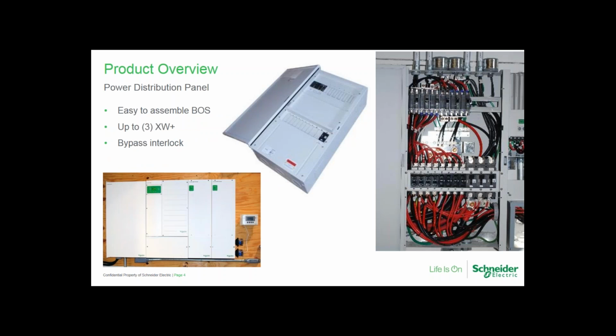The power distribution panel makes installation a breeze for single-unit systems up to and including triple inverter configurations. The standard power distribution panel provides split-phase AC breakers, and we also offer a power distribution panel without AC breakers, so the three-phase breaker kit can be specified. The standard power distribution panel is perfectly suited for dual XW Plus systems when adding the second inverter connection kit and the 120/240 AC breaker kit. The standard power distribution panel is great for single XW systems where the customer may wish to expand at a later date.